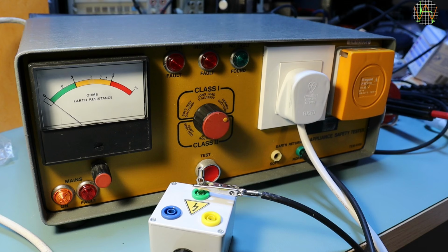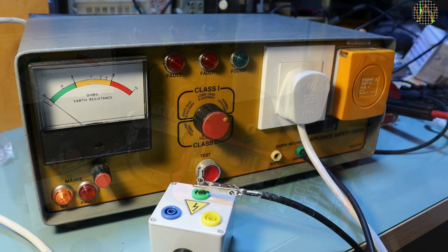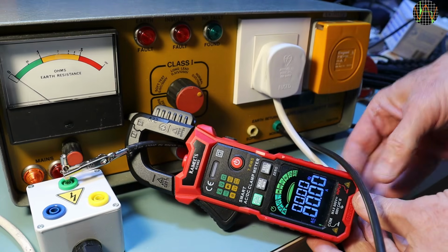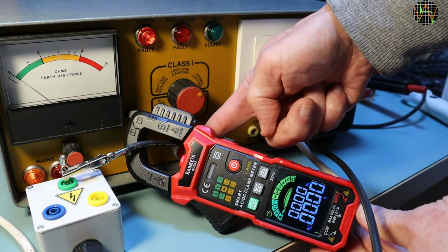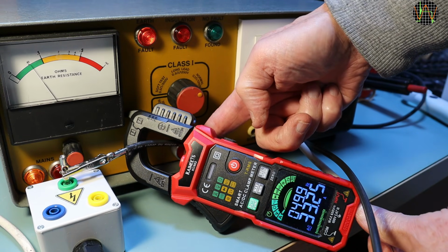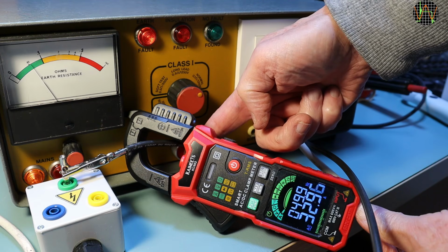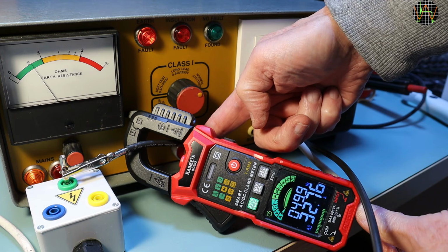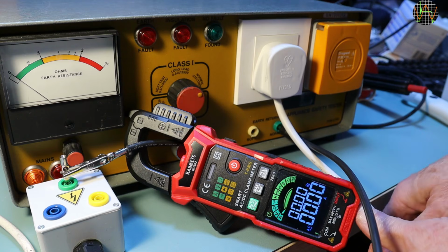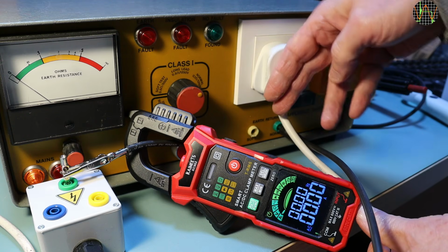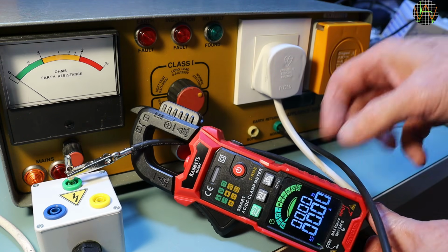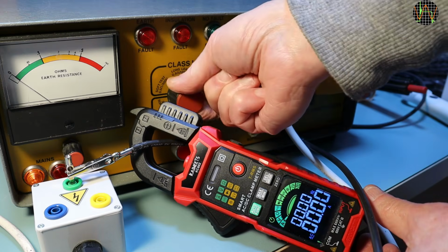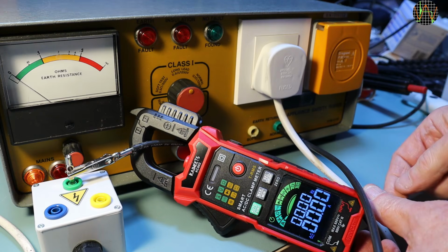How much current did the tester use for these tests? A clamp meter across the earth return will tell. Any bets? Wow, 33 amps in the normal setting. I did not think it was that high, but now I understand that my 0.75 mm square white mains cable is getting pretty hot. There is no automatic stop.